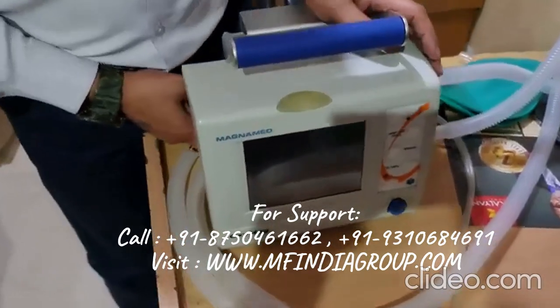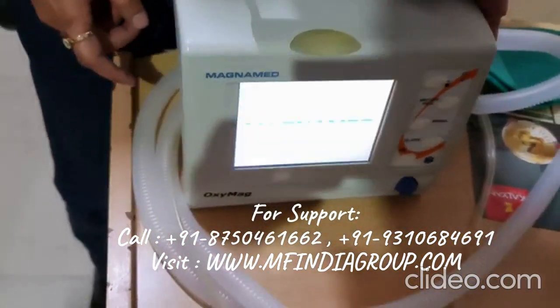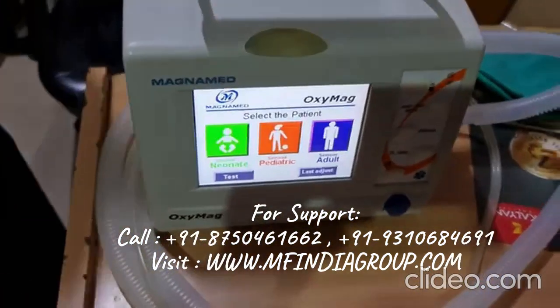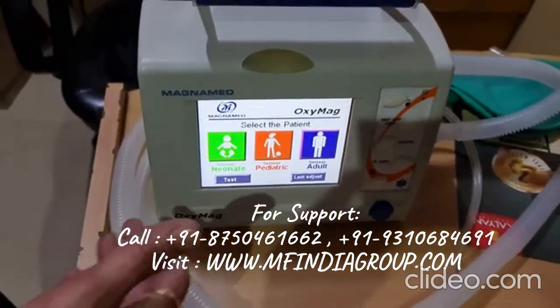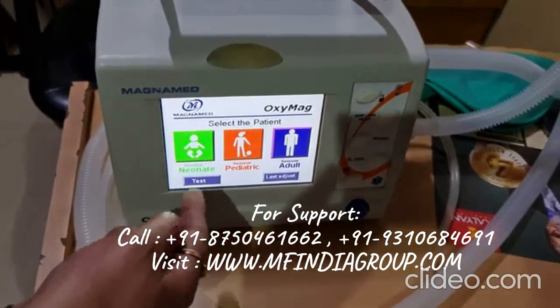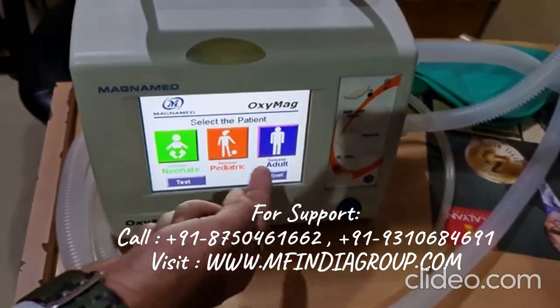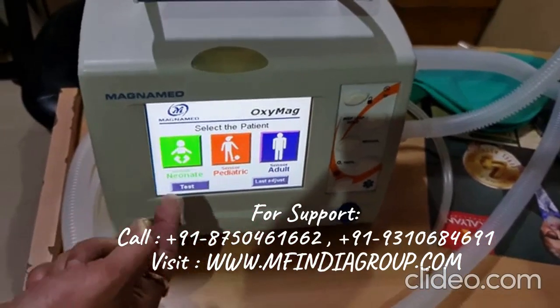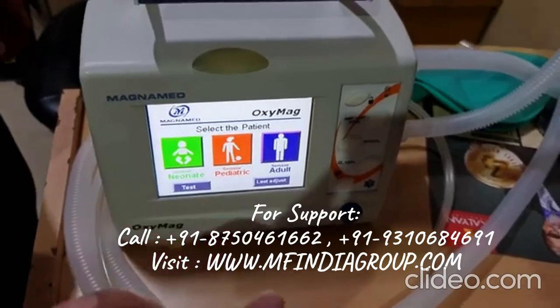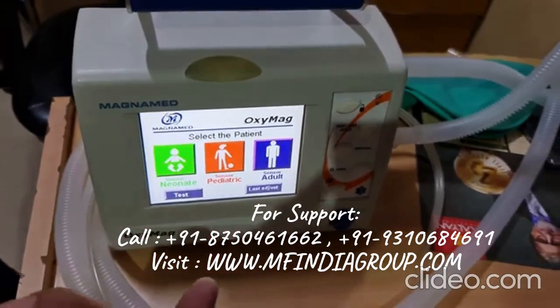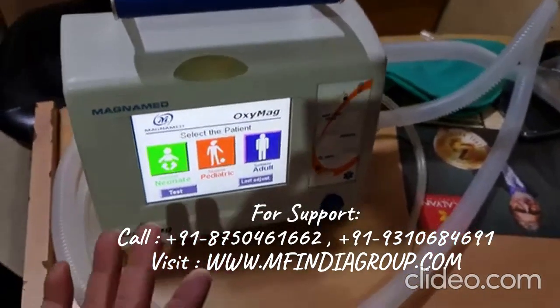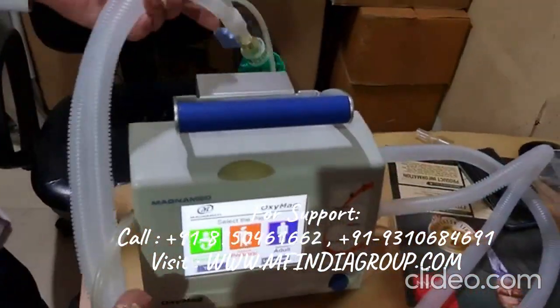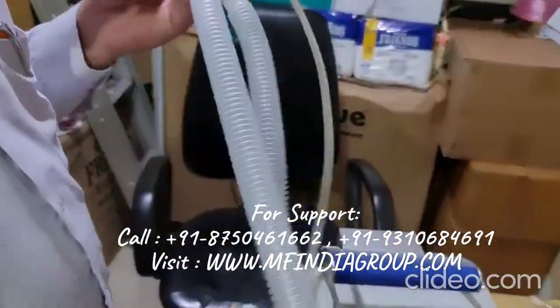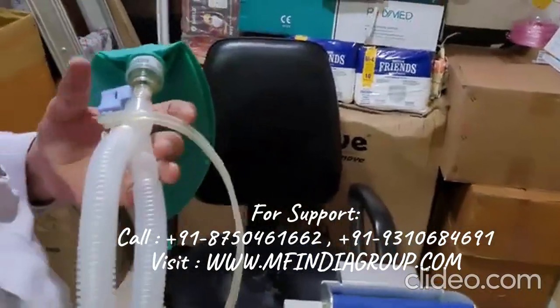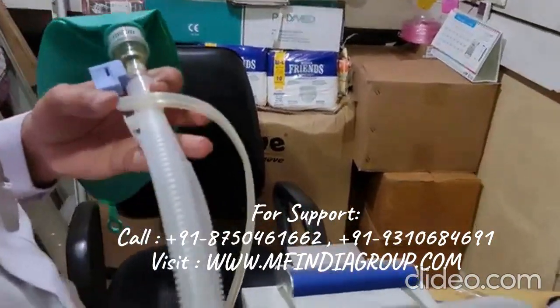So now we start this machine. We have switched on the ventilator. Whenever you switch on the ventilator, it shows all the patients: adult, pediatric, neonatal. According to the patient, you need to select your circuit. If you want neonatal, then you will use 10 mm tubings. If you want a pediatric circuit, you have to connect these 15 mm tubings. If the patient is adult, then you have to use a 22 mm adult circuit.